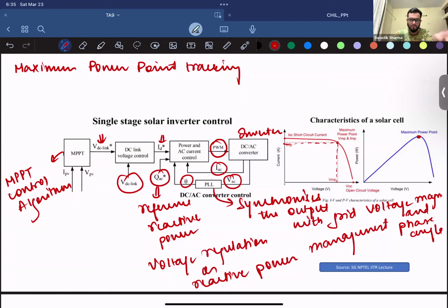But in the forming stage, since there is no AC grid, your voltage should be in voltage control state, because you can't mimic your AC side as you don't have an AC side altogether. And your BESS, which is your energy storage, is then used to mimic the grid conditions, because it can supply power which is not dependent on the conditions prevailing based on the weather or anything else.